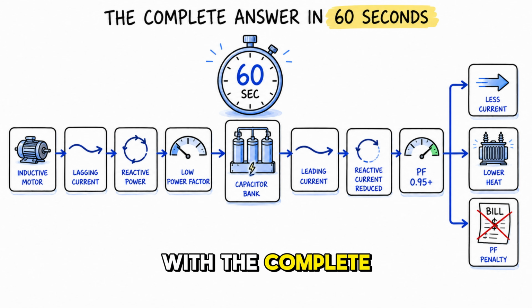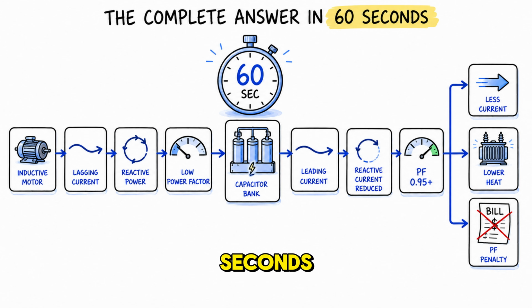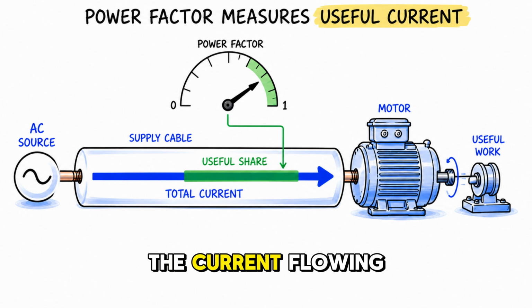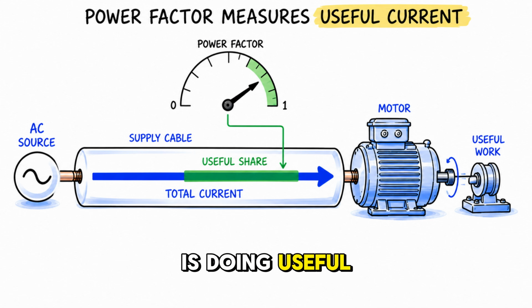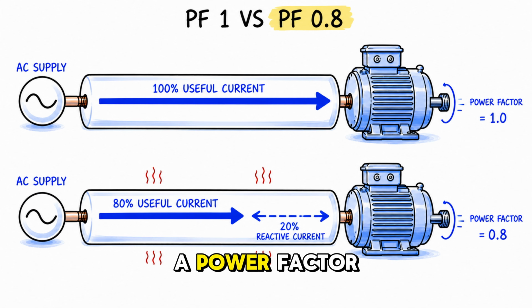Let us close with the complete answer in 60 seconds. Power factor measures how much of the current flowing through a supply cable is doing useful work at the load. A power factor of 1 means every ampere is doing useful work. A power factor of 0.8 means only 80% of the current is doing useful work. The remaining 20% is reactive current bouncing back and forth between the source and inductive loads, doing nothing useful but occupying cable capacity and heating conductors.